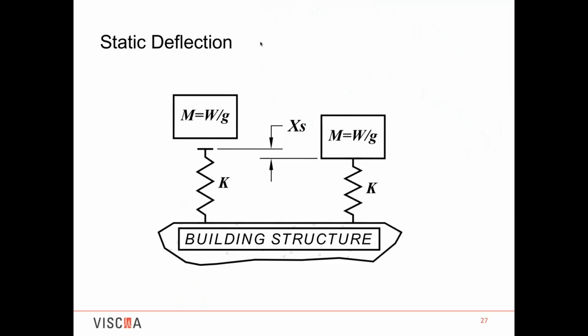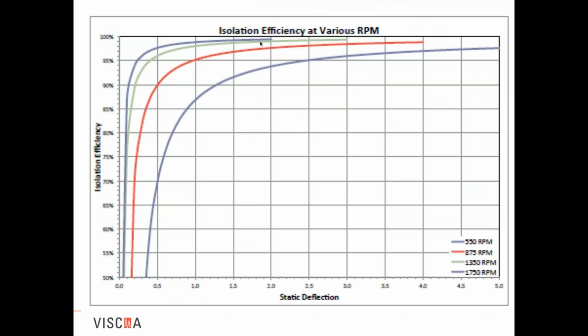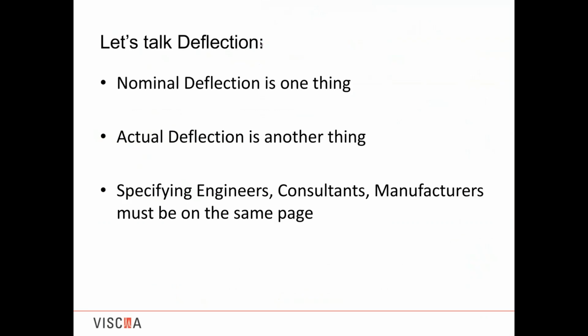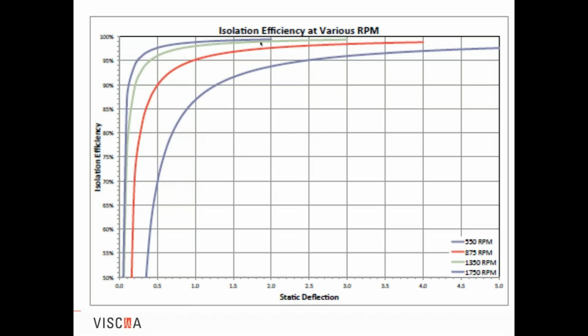But also, before I move forward, I'm going to jump back to this slide again and Angela's discussion of nominal and actual. In general, the members of VISCMA, when we're selecting spring isolation predominantly in this chart for equipment, we're going to be up into the 95 to 100% range. Obviously, as I said, these are all asymptotic to 100%. You can never get there. But in general, so these first two, the green and the other blue, the 1350 and 1750, for this piece of equipment, we'd be selecting a nominal 1-inch deflection.